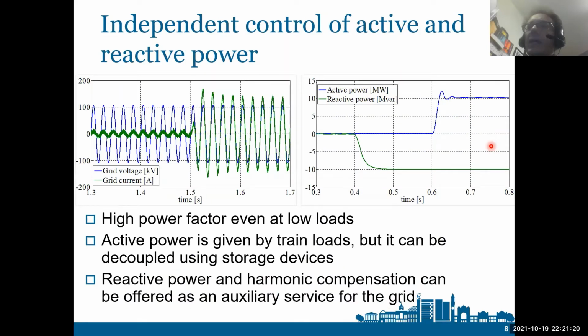An advantage of having a traction power substation with converter is the independent control of the active and reactive power. So in this simulation, I have analyzed the current drawn by the converter on the three-phase side with a step change in the load. Before 1.5 seconds, there is very, very low power, so the converter operates at no load on the railway side, and then there is a step change on the output side. And as you can see, the power factor is maintained equal to unity, whether it is a high load or low load.